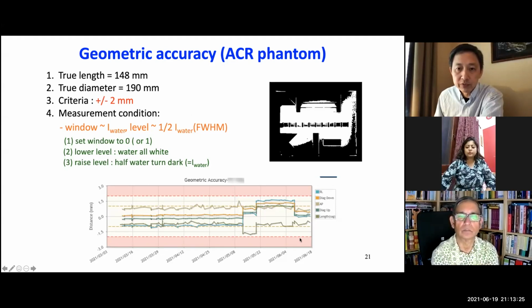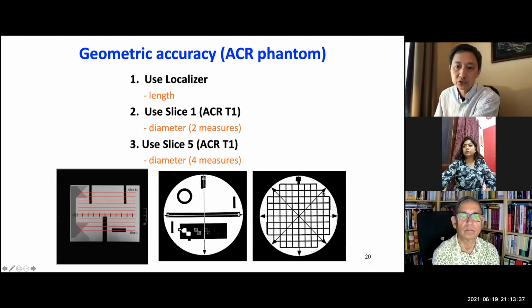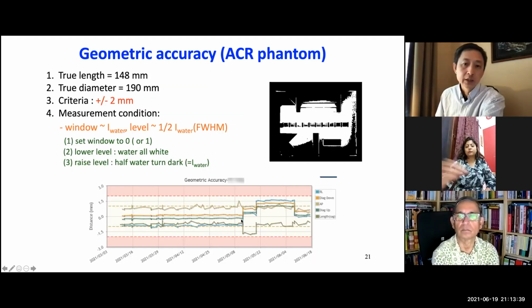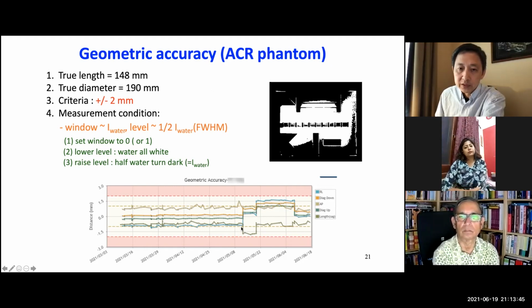And here I show you a result from one of our scanners. You can see clearly there are 5 lines. The 5 lines are the 5 measurements on slice 5. Okay, and you can see the geometric accuracy is off at this time point. What happened was this was a routine PM. After the PM, the engineer came in to do a service, and after the service, they did some gradient calibration, but the calibration was not in a good condition.